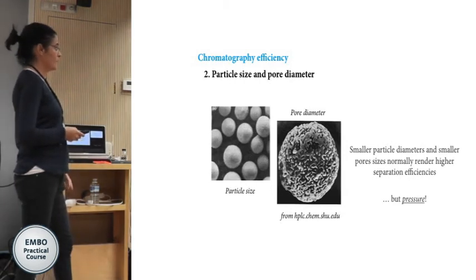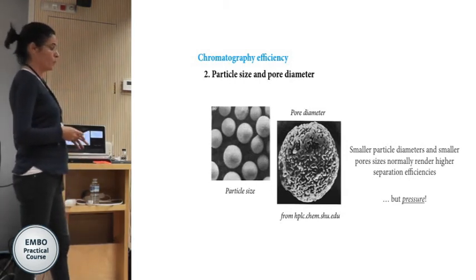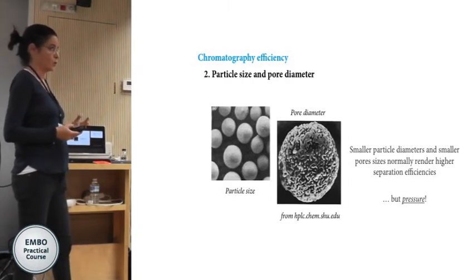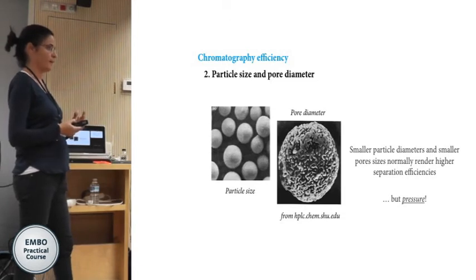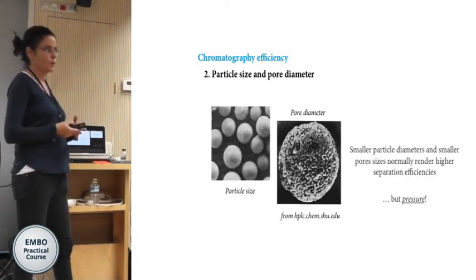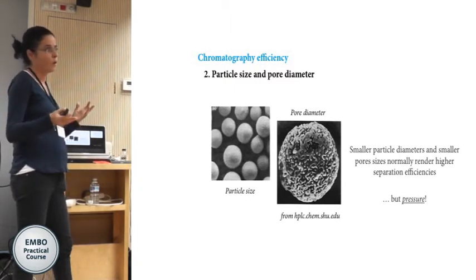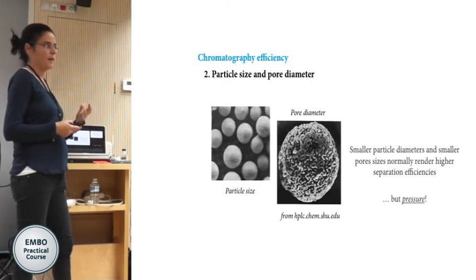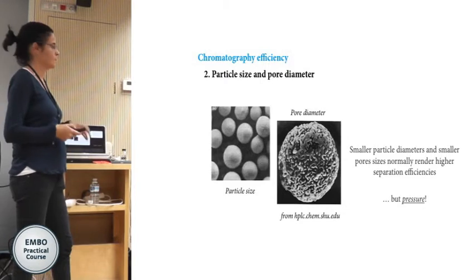Smaller particles and smaller pores give better resolution, but they generate very high back pressure. Depending on the LC system you have, you may not be able to use a very long column because the LC cannot deliver the mobile phase at that pressure.